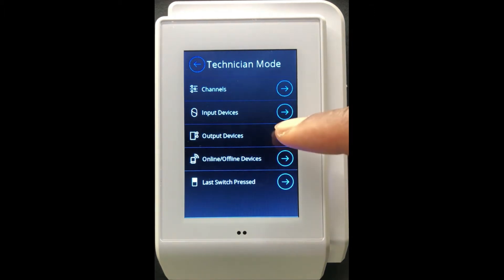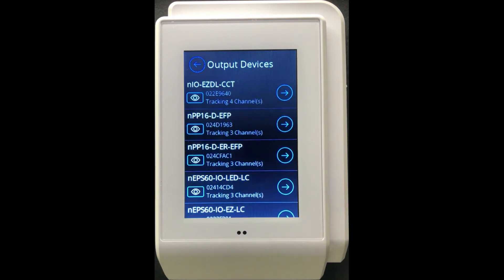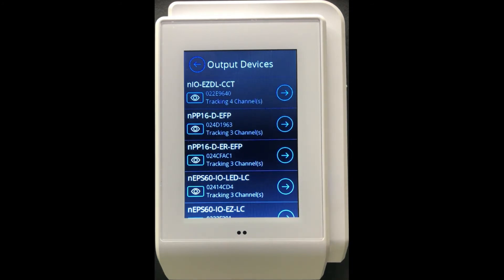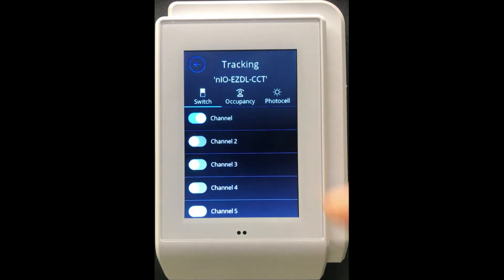From here you can tap on output devices, and that will give you a list of all the output devices currently connected to this NDTC. For example, on this NDTC we have an embedded luminaire that does CCT. Navigating into this luminaire, you should note that this CCT luminaire actually holds two poles — one pole is for intensity and the second pole is for the Kelvin temperature. From here I can modify which specific channels the intensity is tracking and also determine which specific channels the Kelvin temperature is tracking.